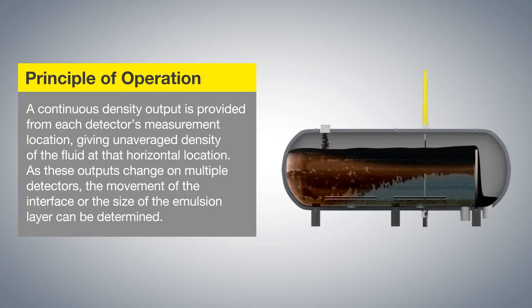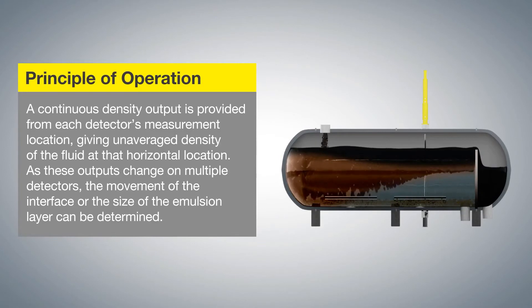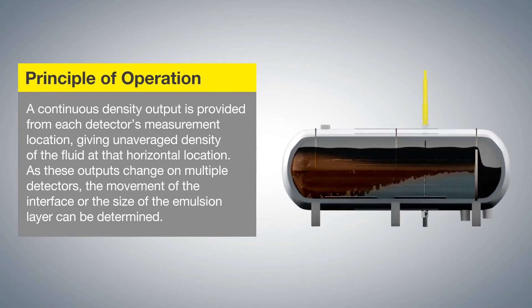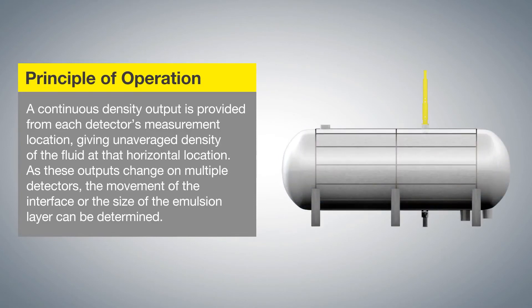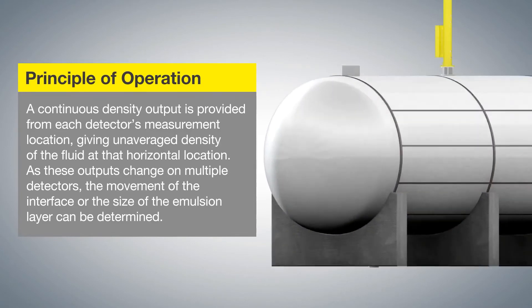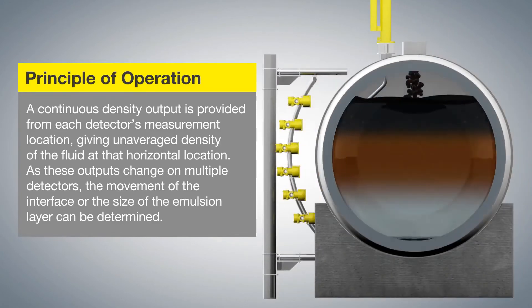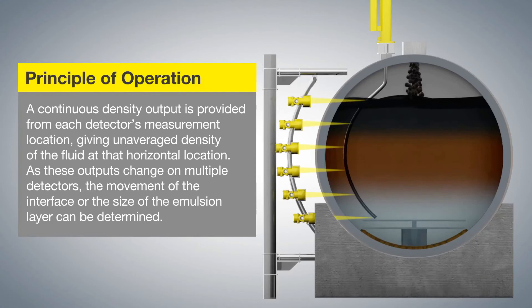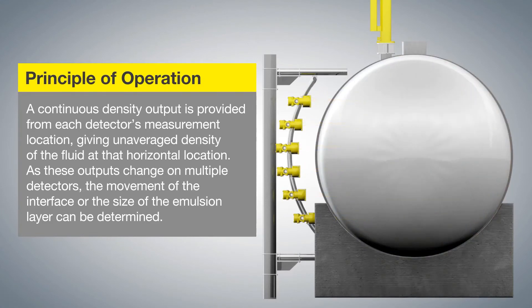Principle of Operation: A continuous density output is provided from each detector's measurement location, giving unaveraged density of the fluid at that horizontal location. As these outputs change on multiple detectors, the movement of the interface or the size of the emulsion layer can be determined.